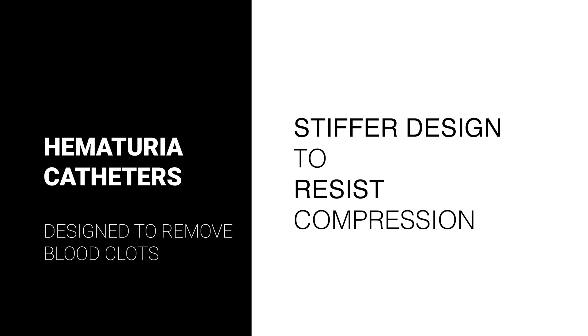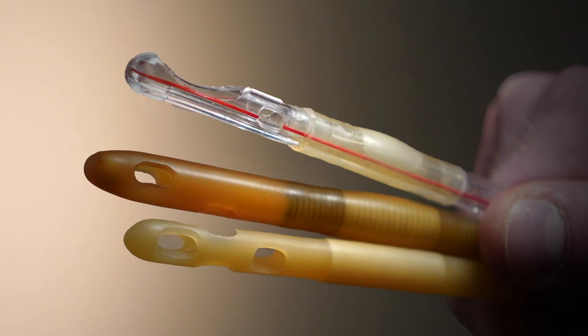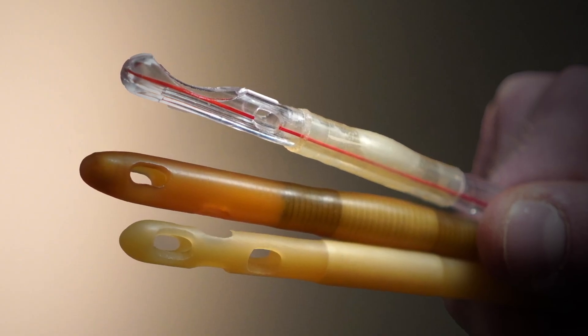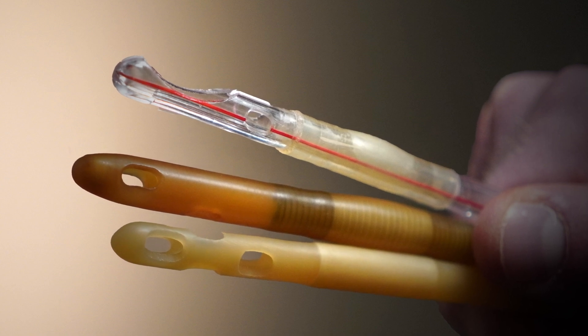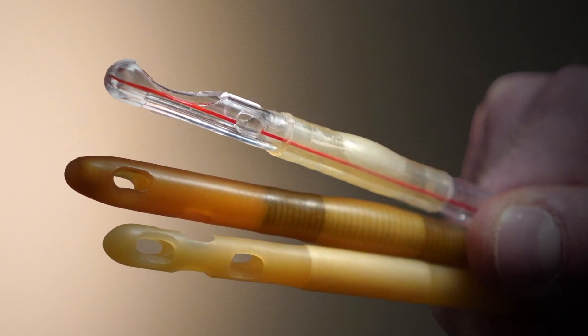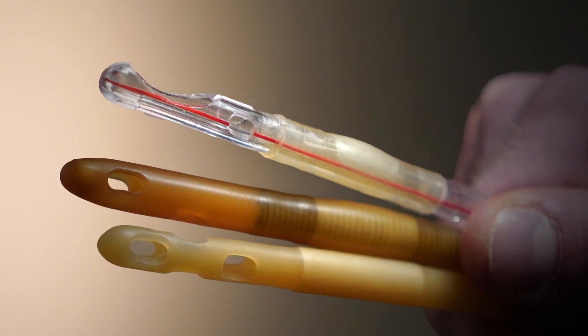So I think that's a good segue and brings us to hematuria catheters. What is a hematuria catheter? Hematuria catheters are specifically designed catheters to help manage hematuria and blood clots. They come in a two-way and three-way versions. They are generally made of stiffer material that resist compression and have an internal nylon or metal springs that help resist compression from irrigation or aspiration. When you're pulling out clots and aspirating that tube, it prevents that from collapsing down and decreasing the flow of the clots.